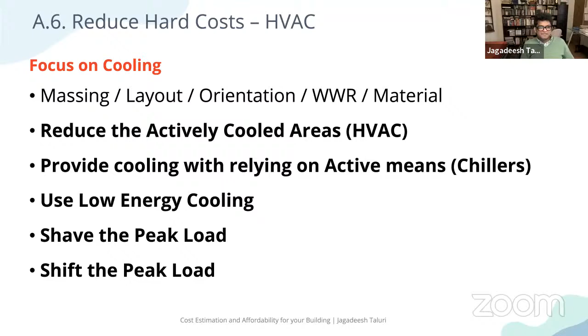For example, in this Suzlon One Earth building, the original load without any of the measures was 1905 tons. And we used louvers, double glazing, insulation, LED lights, heat recovery, everything possible that we could. Still, we could not go beyond 37% optimization. The one way we could get to LEED Platinum or TERI 5-star, which the client wanted at that time, was to reduce our cooling load or the chiller sizing.